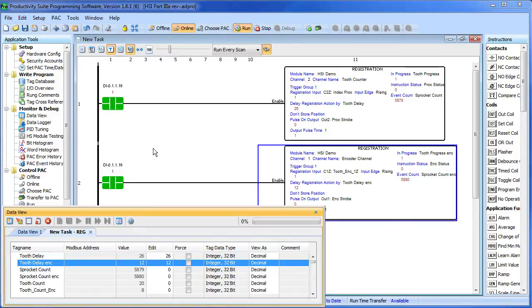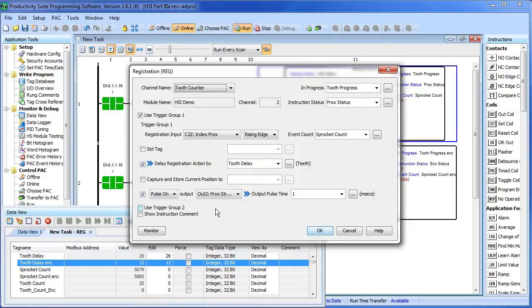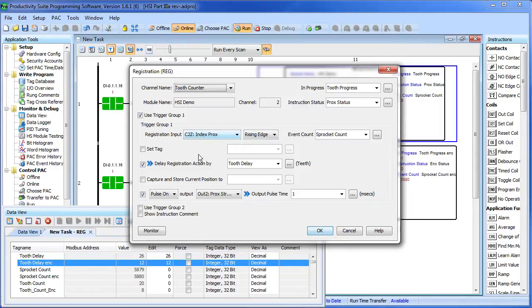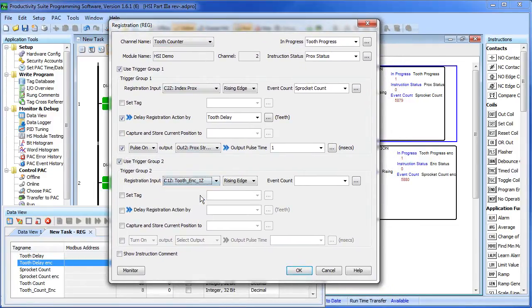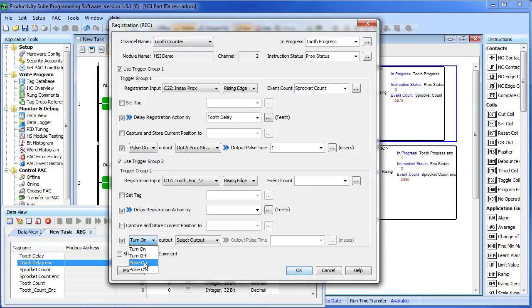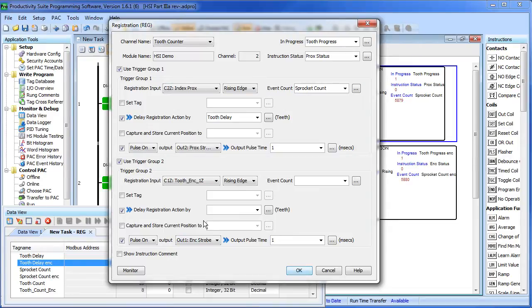Let me show you one more thing. The example we just did used two different registration instructions triggering off of different strobes. Could we have done all of that with one registration instruction? Yes, here's how. Back in the registration instruction for the proximity sensor, we told it to pulse the LED after a delay after the rising edge of the index pulse of the proximity sensor. Well, look here – there's a second trigger group. We could have simply said – trigger on the other input – the encoder input in this case – save it to some event count after some other delay, pulse our other output for 1 millisecond. So with two independent trigger groups, you can actually do two different registrations with one instruction.